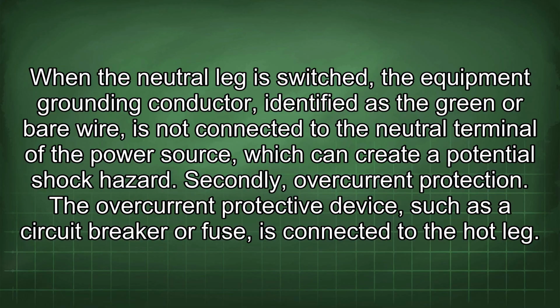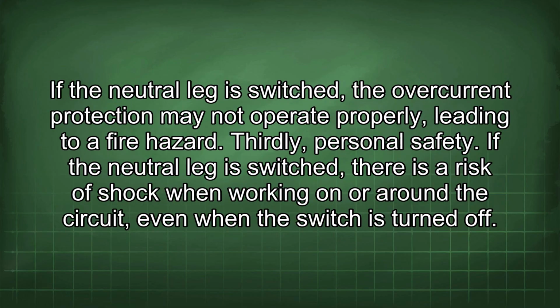Secondly, overcurrent protection. The overcurrent protective device, such as a circuit breaker or fuse, is connected to the hot leg. If the neutral leg is switched, the overcurrent protection may not operate properly, leading to a fire hazard. Thirdly, personal safety. If the neutral leg is switched, there is a risk of shock when working on or around the circuit, even when the switch is turned off.